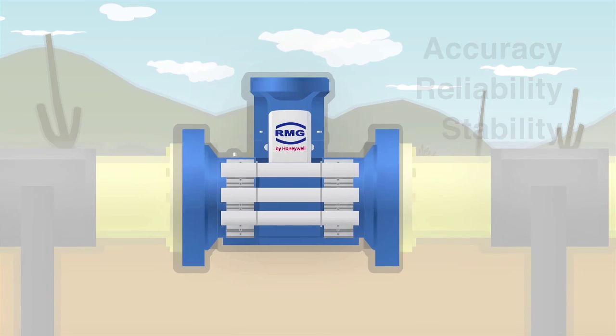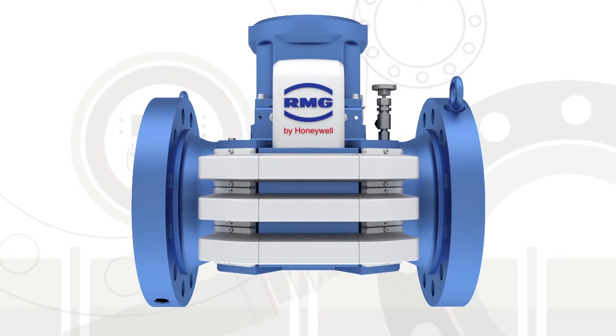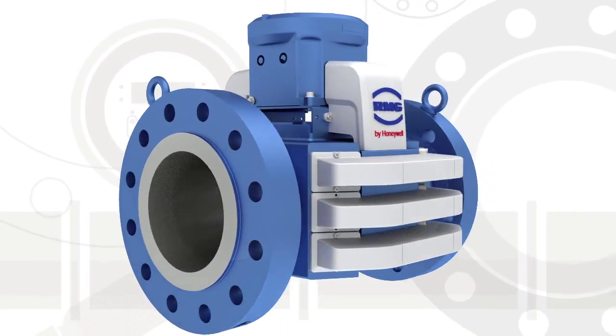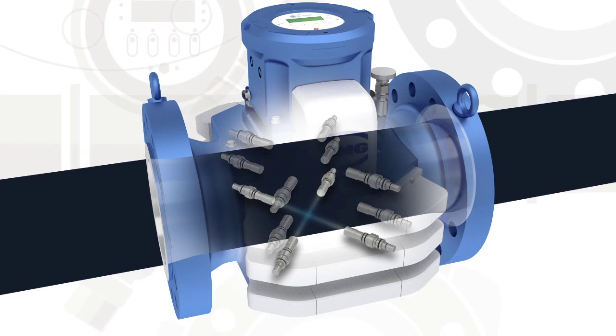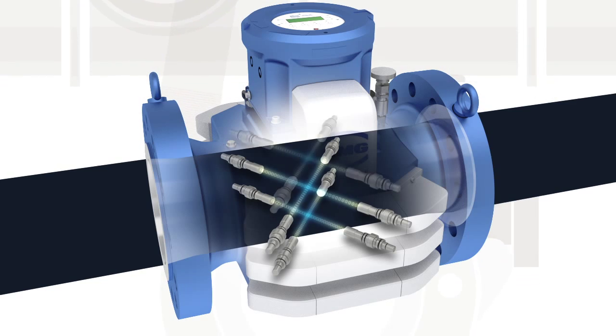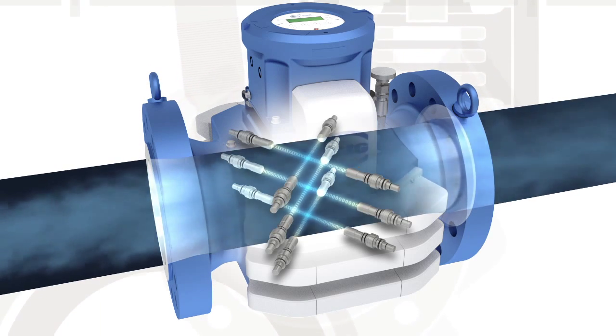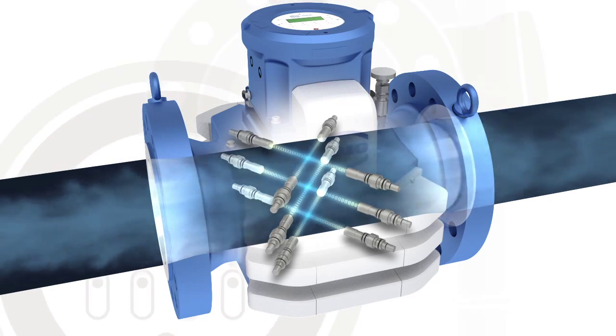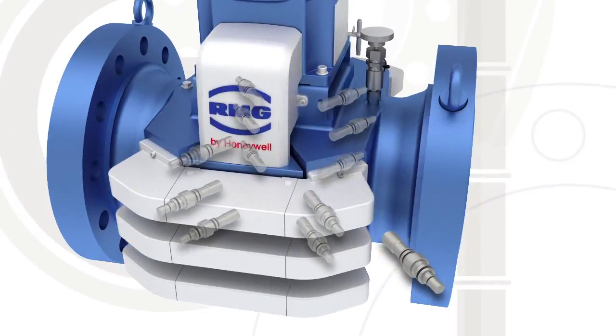The GT 400 has a proven record of accuracy, reliability, and long-standing stability in the most demanding environments. Our innovative direct path measuring technology performs transit time measurement by using six measuring paths on three planes. This X-crossed three-dimensional arrangement of the transducers directly measures gas swirl, cross flow, and asymmetry better than a reflective bounce path approach, ensuring superior performance under changing gas flow conditions.